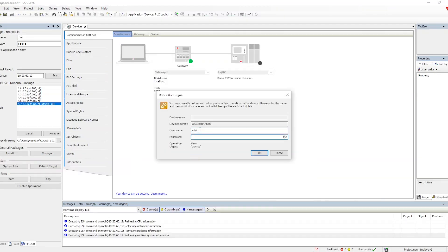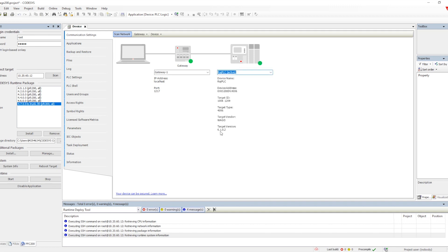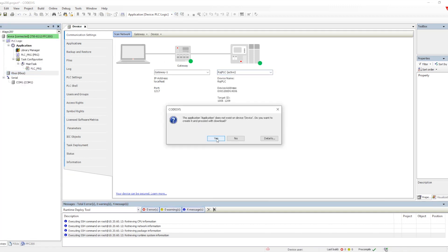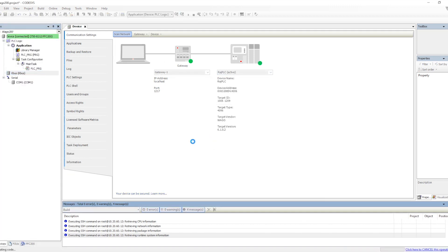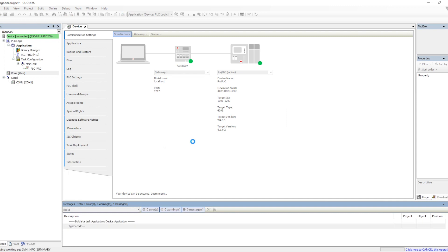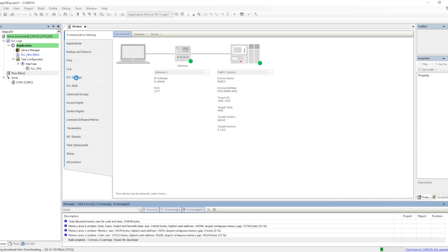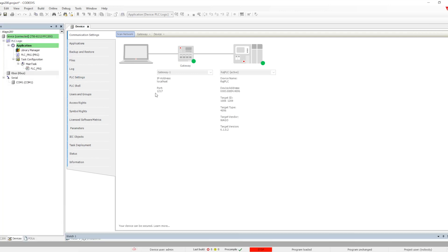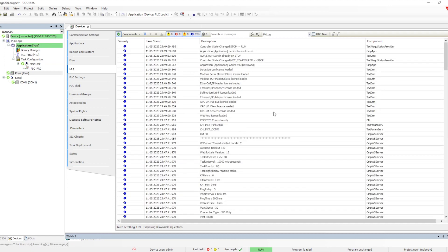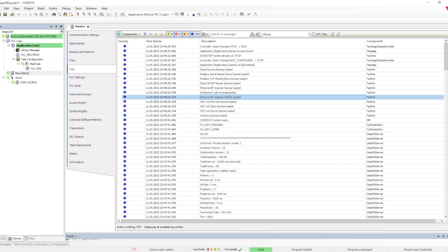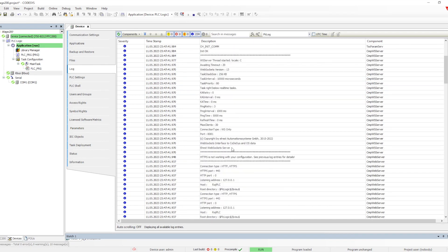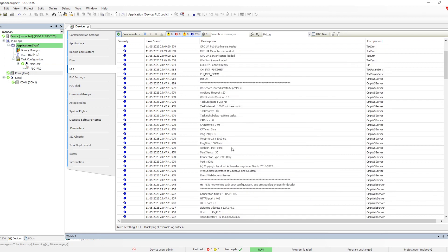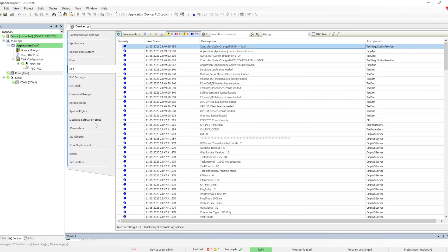We need to always check that the PLC runtime is selected. Once we do that we will be able to scan the PLC and we need to put the admin password which is admin and WAGO, same here also for the user management, and then we can download. In this way with the device description of WAGO we can connect with the PLC. All the licenses and everything will be there as it is by default coming with the PLC.